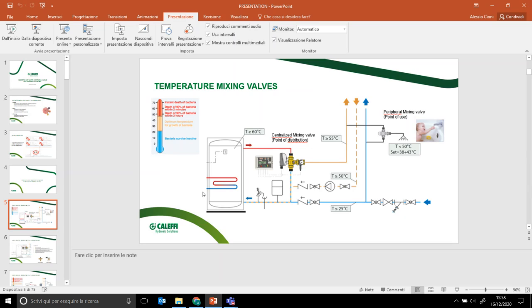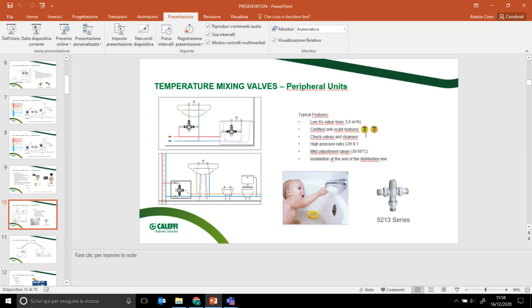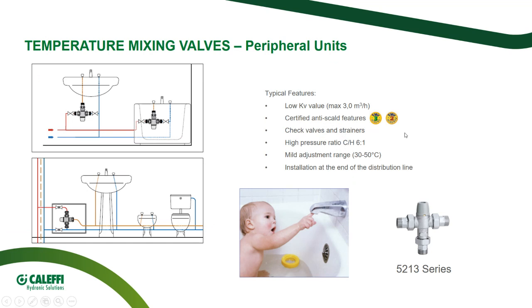Okay. Do you have a fail-safe on this TMV? If, for example, the cold water fails, is that going to switch off automatically? This one? Yeah, of course. And this performance is certified by a third party. Before we mentioned TMV3 and TMV2 certifications, and these are third-party certifications that state officially that the valve complies with some European norms, in particular from the UK, but also from Europe, for anti-scald performance. TMV2 is the anti-scald performance feature referred to residential types of application like dwellings. TMV3 is even more restricted and related to healthcare buildings. So the parameters of the test are very, very restricted. It is very difficult to comply with TMV3 and TMV2, but Caleffi devices comply.